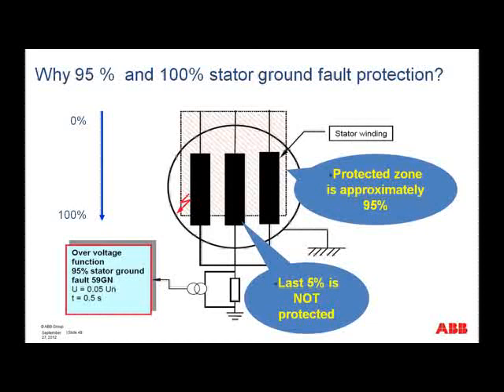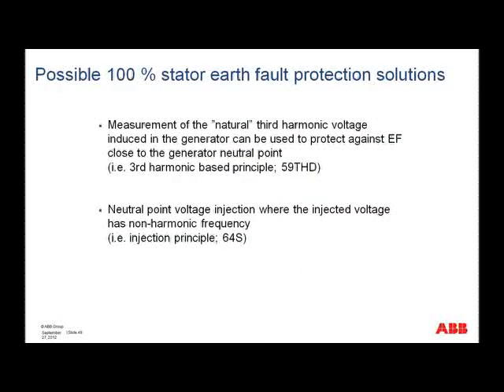And that's why we talk about 95% stator ground fault, because whether we're using the voltage-based or the current-based, we can't get to really the last 5% just before the star point. Of course, we need to make a plan how to get around this. And there are two ways of achieving the 100% stator earth fault protection. The one is the third harmonic principle.